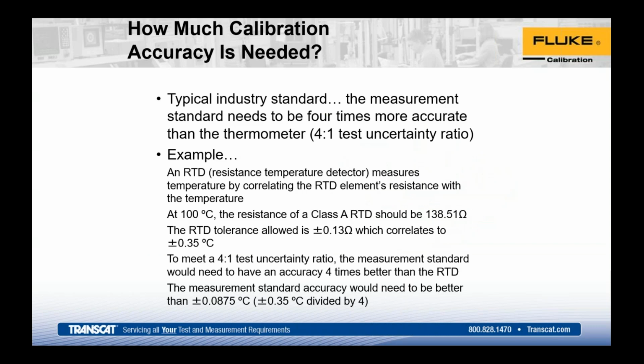So again, how much calibration accuracy is needed? As I've talked about a couple of times, TUR is usually 4 to 1. In this example, we're going to assume we're calibrating a typical RTD, a 100 ohm DIN class A, so it's going to be 100 ohm at 0 C. We should be getting approximately 138-ish ohms out, which correlates to about 100 degrees C. We're trying to calibrate it to 0.13 ohms, which correlates to 0.35 C. In that 4 to 1, we take 0.35 divided by 4. So our heat source stability, uniformity, reference standard, and reference readout all need to culminate to 0.0875 or better in order to achieve the 4 to 1 ratio we're looking to keep in this process for the DIN class A.